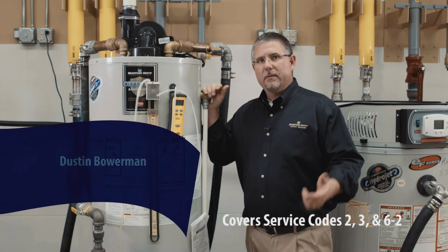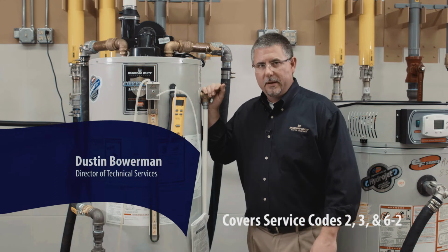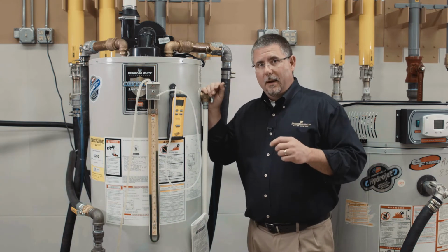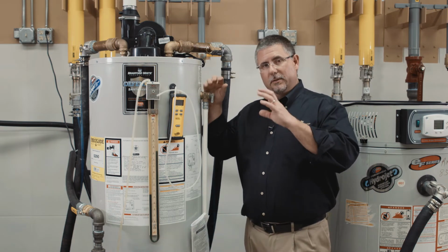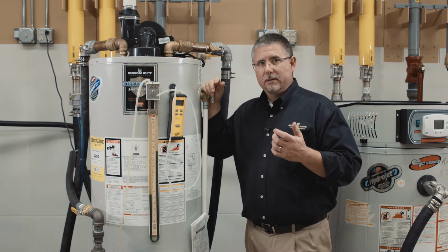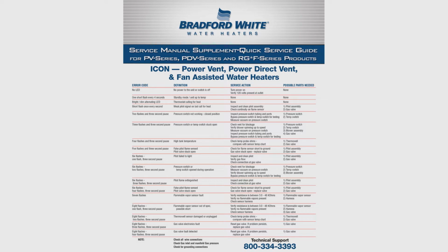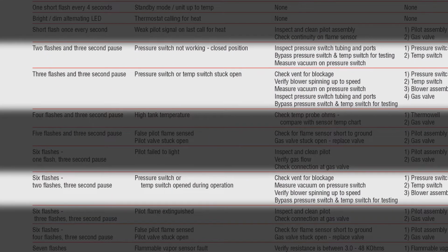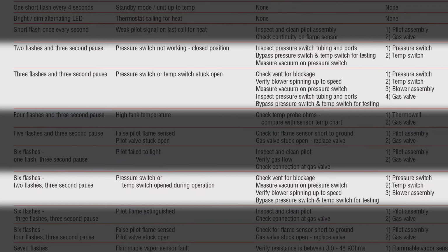Fan assist, power vent, and power direct vent water heaters all have a fan or blower assembly on top. Inside the blower assembly there's a service panel, a couple of safety circuits, and 3 specific error codes: a 2 flash, a 3 flash, and what I call a 6-2 flash.